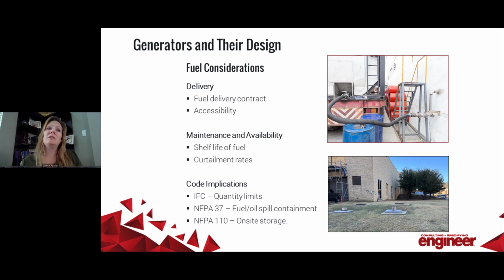And then in addition to that delivery, critical facilities such as hospitals really should have contracts with the local suppliers to be on a preferred provider that would meet those additional AHJ requirements for having the ability to obtain fuel as a first priority. When you're talking about diesel, maintenance is a concern. And I'm not talking about your typical preventative maintenance of mechanical components or servicing of equipment. I'm talking about the shelf life of fuel.